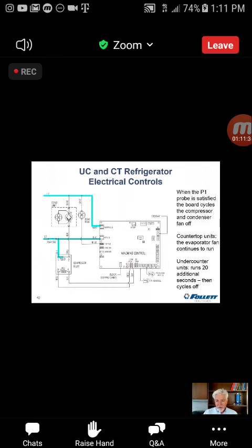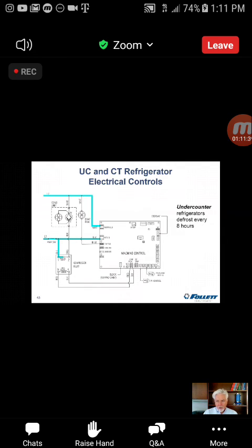The under-counter units do operate to a degree pretty much the same way, but just as a precaution, in case these are in rooms that are small where the temperature tends to rise, we see that in hospitals in different locations, they have a defrost cycle. It is simply an air defrost. All that happens is 3 times a day, every 8 hours, the unit will go into its defrost cycle, and all that means is that the compressor gets shut down and we energize the evaporator fan motor.